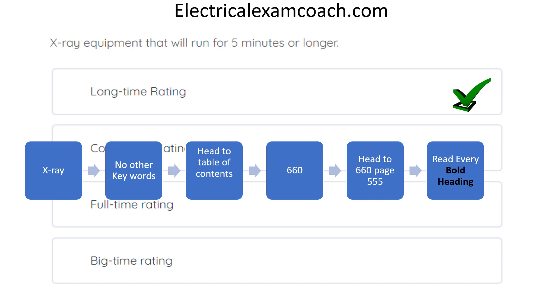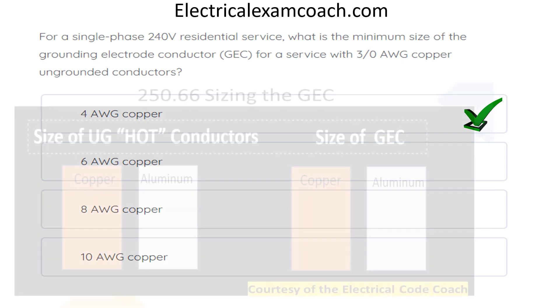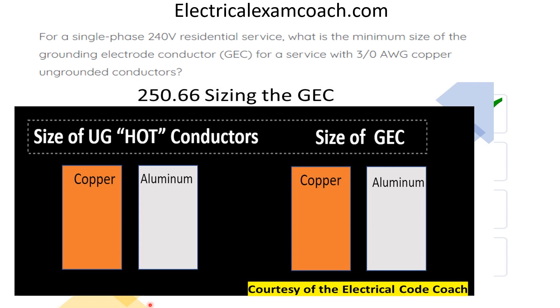There are many angles you can tackle a question, and I want to teach you a way of thinking and structure that works both on exams and in the field. For a single-phase 240-volt residential service, what is the minimum size grounding electrode conductor for a service with 3-aught copper ungrounded conductors? The correct answer is 4 AWG. First, ask whether the question mentions the type of electrode. It does not, so we use Table 250.66 at face value. Select from the copper side for copper ungrounded hots, and cross over to the copper side for the copper grounding electrode conductor.